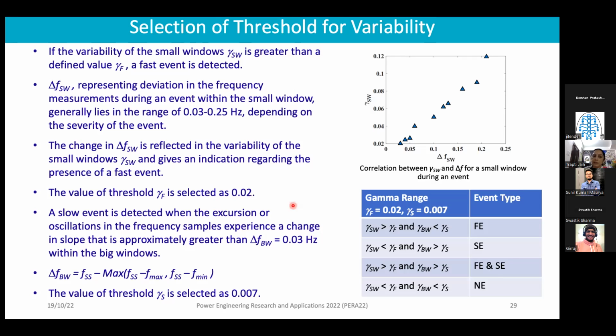Now, when we observe this for a slow event, we see that if a slow event is happening, there will be a change in the slope of the frequency. This slope was identified, and this value is considered at 0.03 hertz.